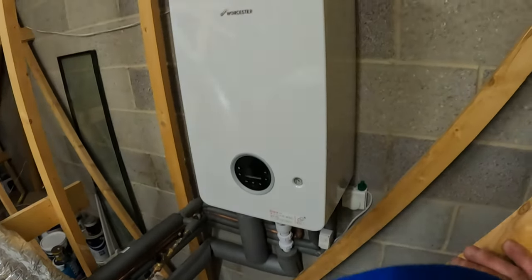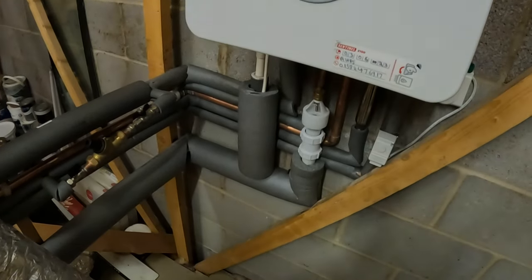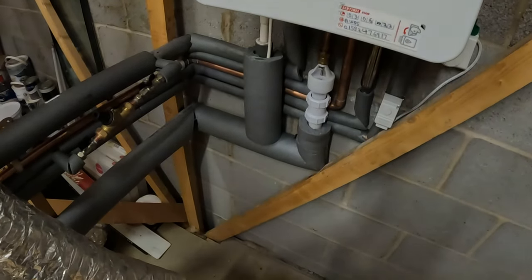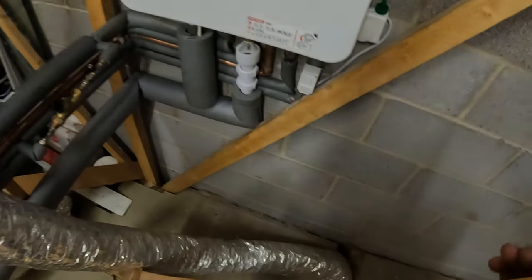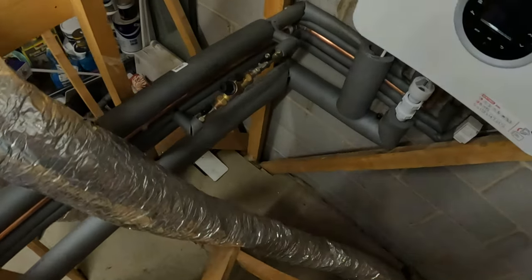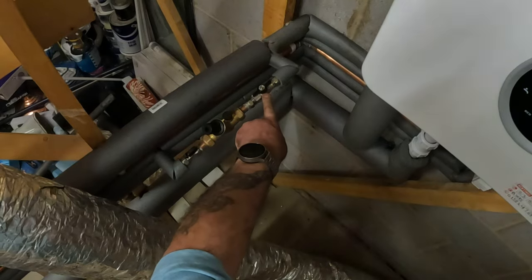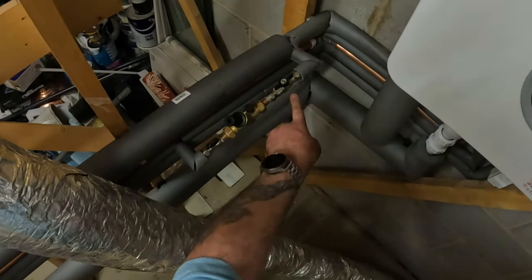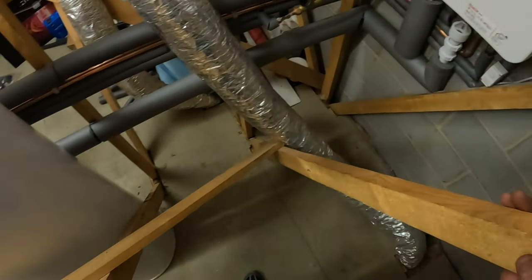So this is a Worcester 2000 with a vertical flue. A tundish for the PRV. Frost protection just there. This is my automatic filling with a non-return valve to stop any back siphoning going back into the water main. All lagged.